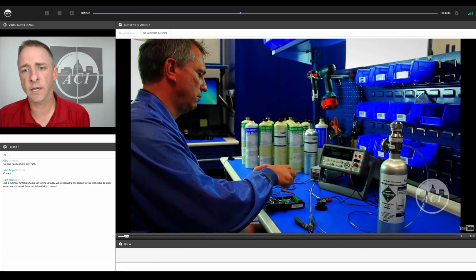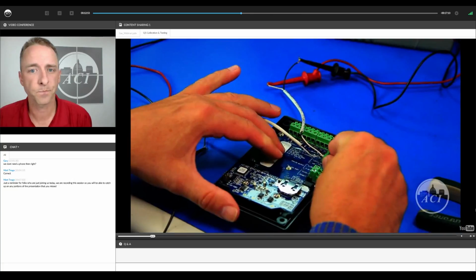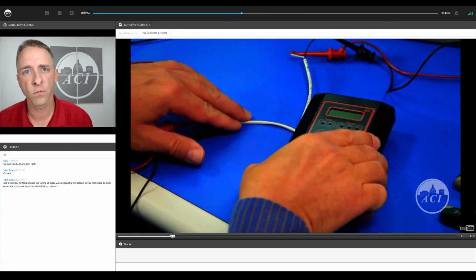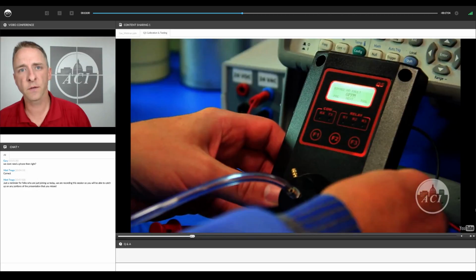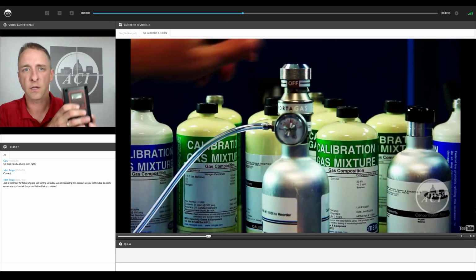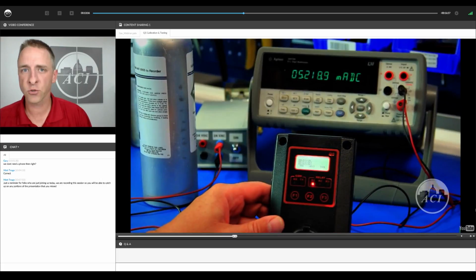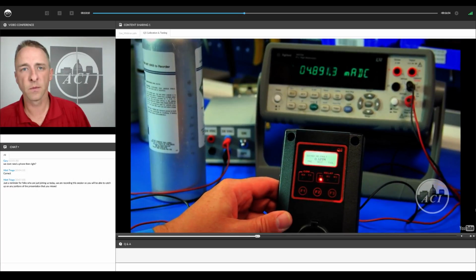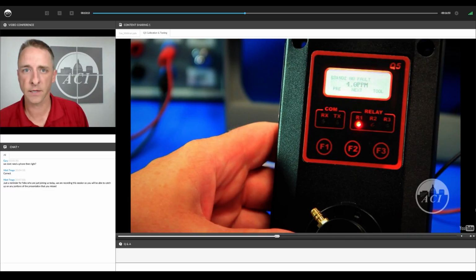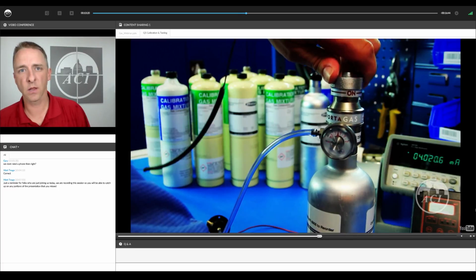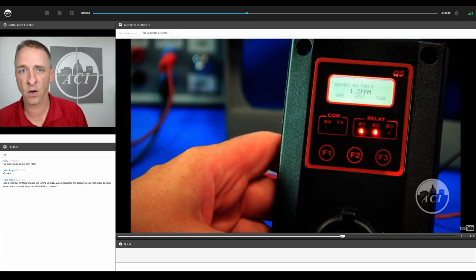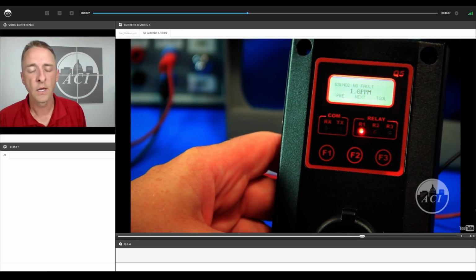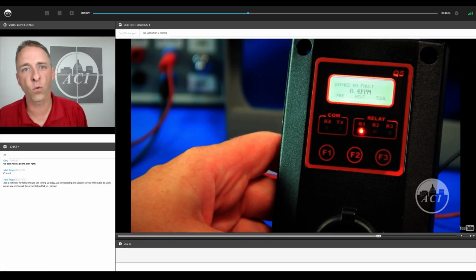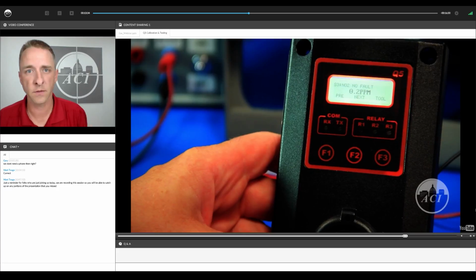I'm going to show a quick video that shows Dave Wisey, one of our technicians, testing and calibrating these Q5 sensors. We test before shipping, and I wanted to talk about the life expectancy of these sensors. Because these sensing elements are electrochemical, there's a chemical reaction when the gas is detected in the space. As a result, the sensor will wear out over time. So these sensors do have a lifespan, and the higher the concentration of gas that's present in the air, the faster these sensors will wear out. Typical life expectancy for these units is 4 to 6 years, but that can be longer or shorter based on the actual readings of gas that's present in the air.